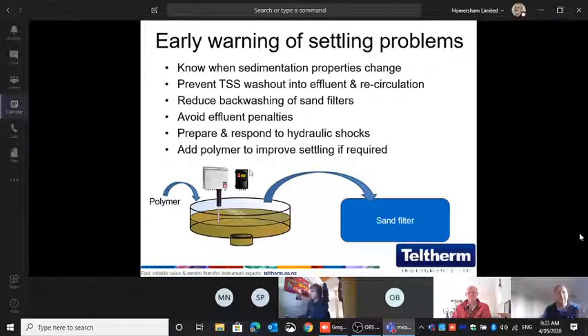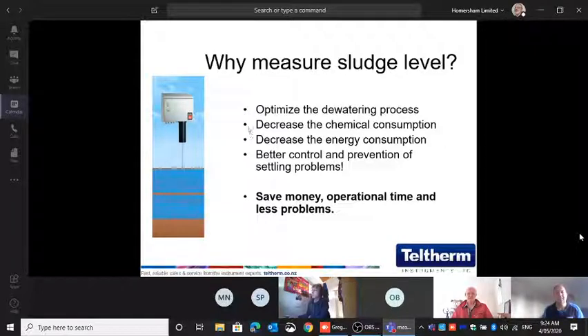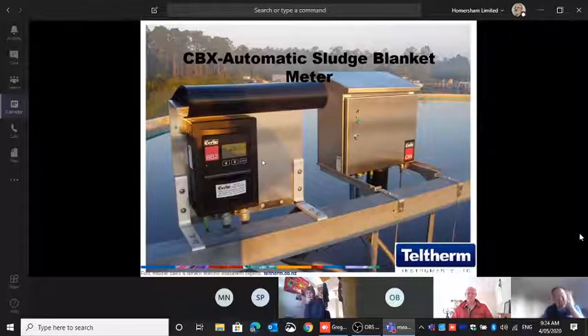The thing is, of course, early warning of settling problems. That's where these units come into play. If you got a beautiful site, where you got good settlement, then anything works. You can use a sludge jet, you can use an ultrasonic, everything works. It's when problems start to happen. That's when you want to see the units actually giving you the data constantly. That's what makes this unit valuable, because when things go wrong, this unit will keep giving you information. So basically, if you optimize in the beginning, the rest will follow. Like I said, if you do it well in the beginning, the rest will follow automatically.